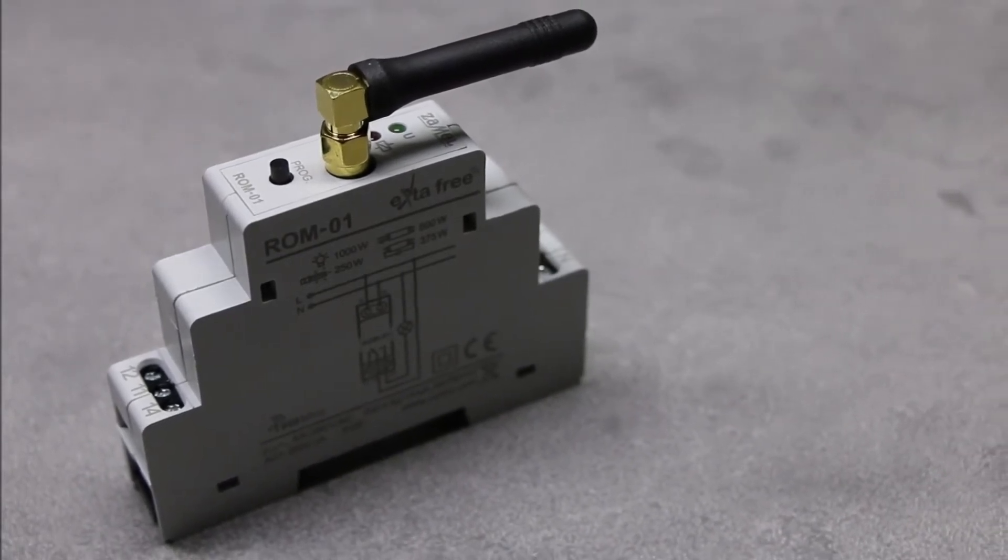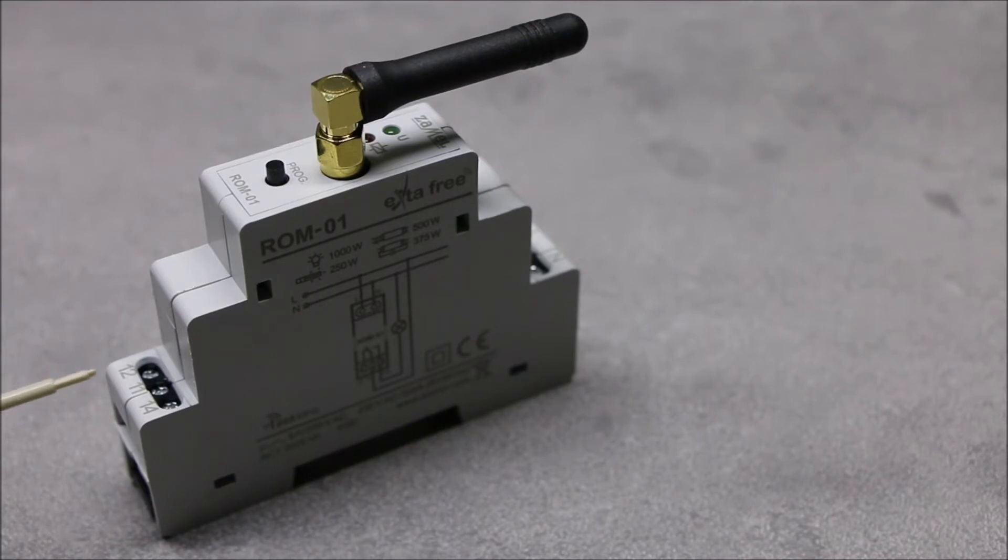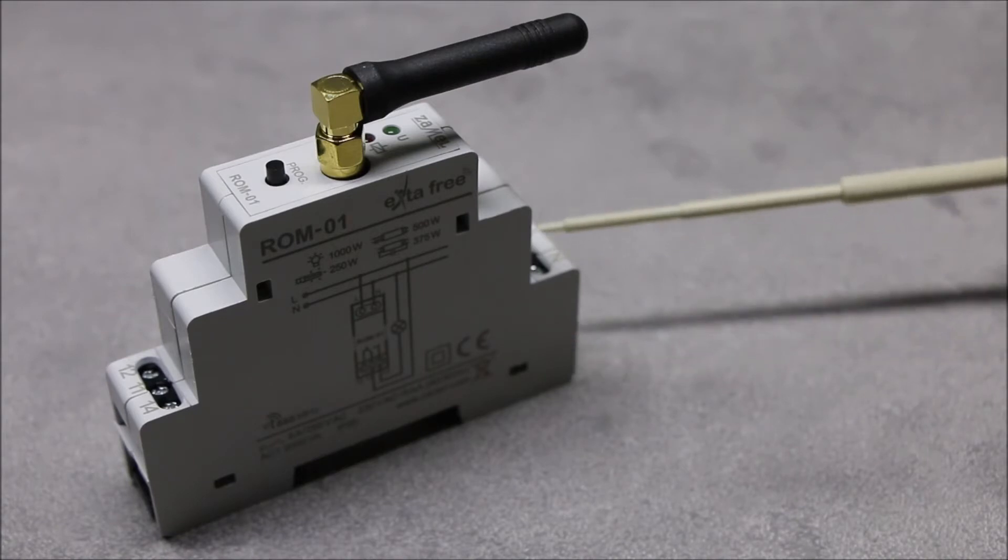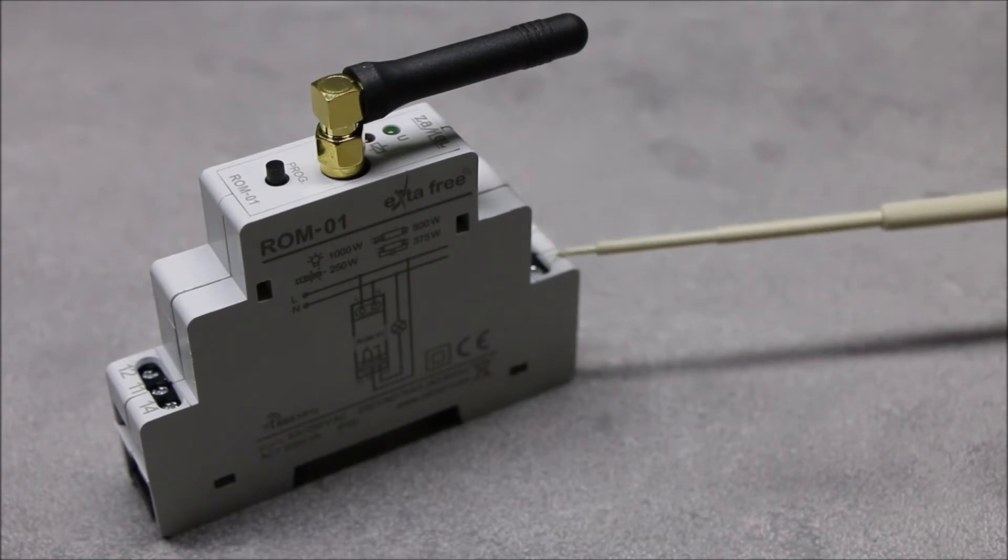The receiver outputs are switching relay voltage-free with maximal load of 16 amperes for devices supplied with 230 volts. ROM01 requires voltage supply in the range between 190 and 250 volts AC.